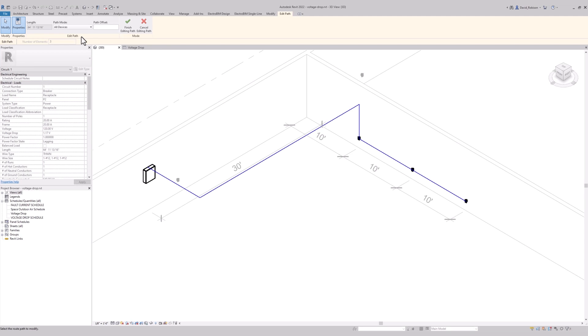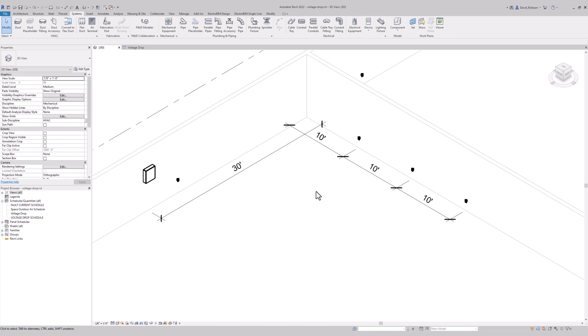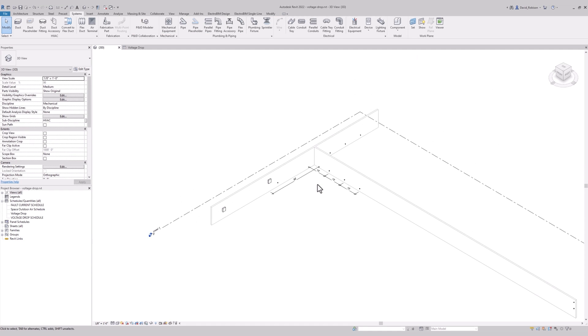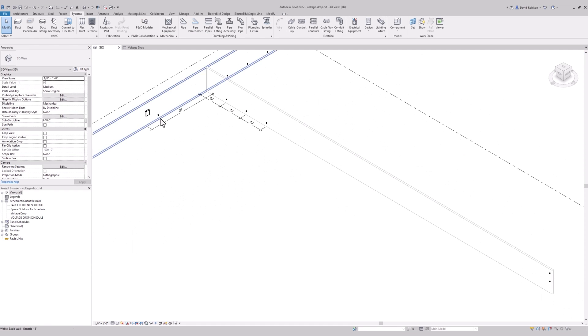One place Revit is going to struggle with voltage drop is what to do with circuit length and load together. On that circuit I was looking at, we have three receptacles and one distance, so it's assuming all of the load is at the farthest receptacle. If you have a single point load that's going to work, but if you have multiple loads, that's not going to work as well. I set up a sample here to demonstrate — some receptacles are close to the panel, and some are farther away, enough distance that we can start to see some voltage drop.